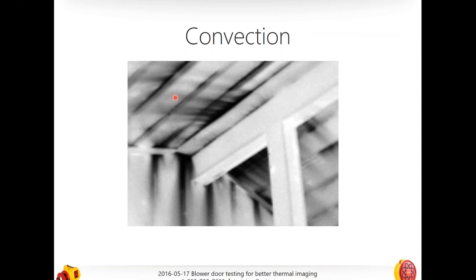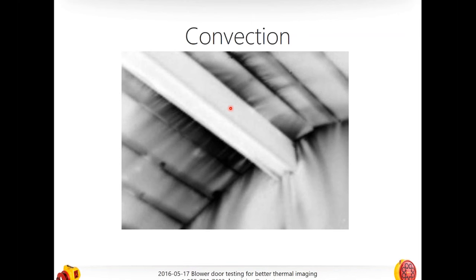Here we can see another more profound line — tongue and groove wood slat ceiling. You can see the lines on the sidewall as well, with actual cracks moving through. This would not have been obvious had we not run the blower door. You can also see some seriously exaggerated lines in one area compared to another, indicating really heavy leakage there.